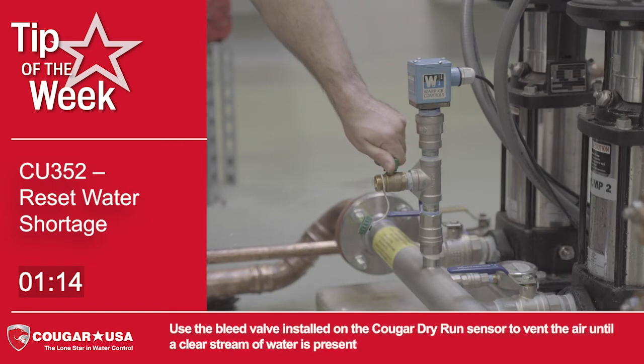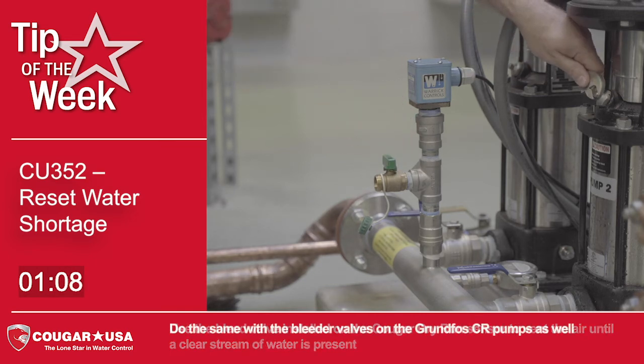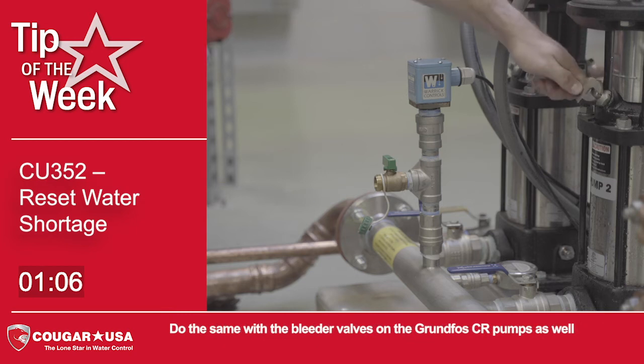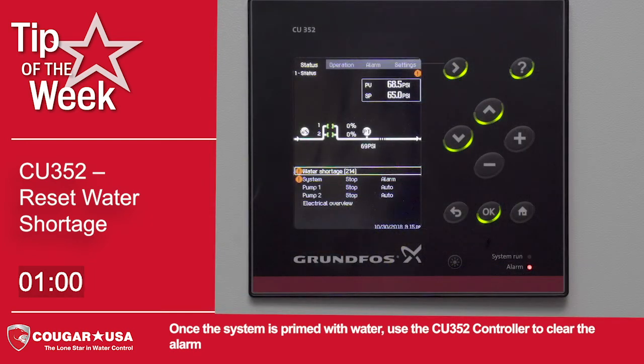Use the bleed valve installed on the Cougar Dry Run Sensor to vent the air until a clear stream of water is present. Do the same with the bleeder valves on the Grundfos CR pumps as well. Once the system is primed with water, use the CU352 controller to clear the alarm.